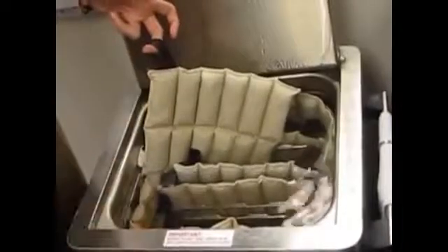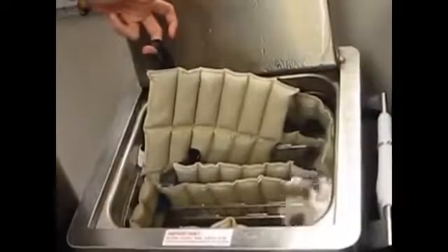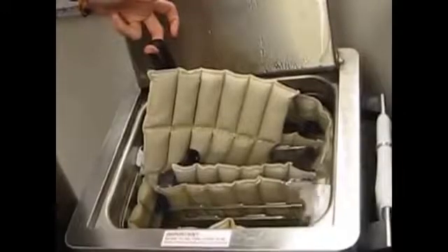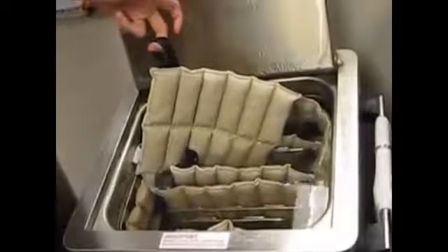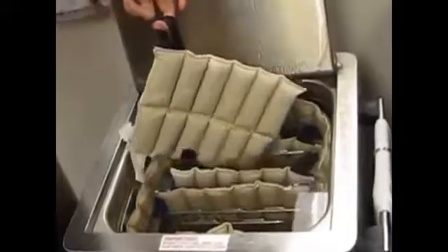The gel is contained in a set of separated fabric pockets so that the whole pack is flexible and the gel is confined. They are heated by being placed in a special tank of water warmed to 70 to 80 degrees Celsius by an electric heater controlled by a thermostat. It takes about 2 hours to become fully heated from cold but less when reheated.